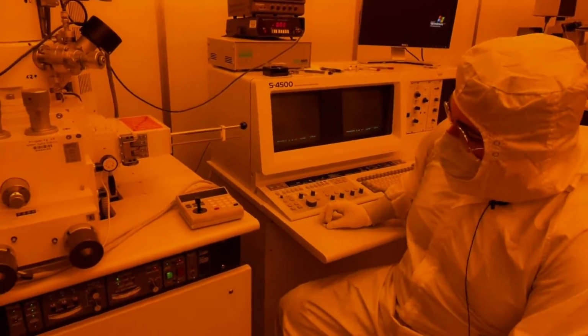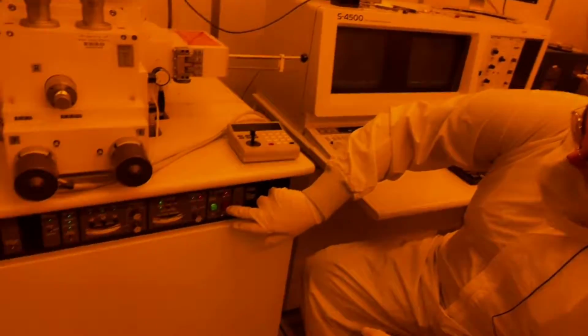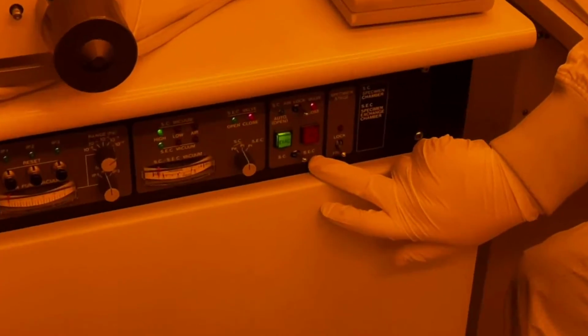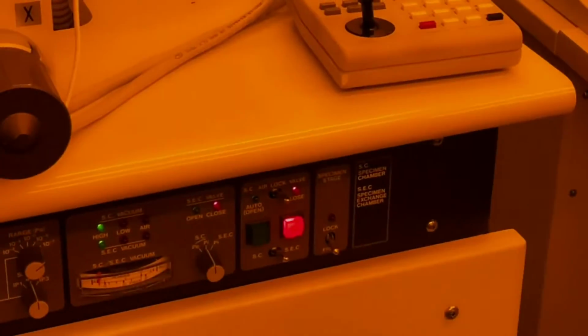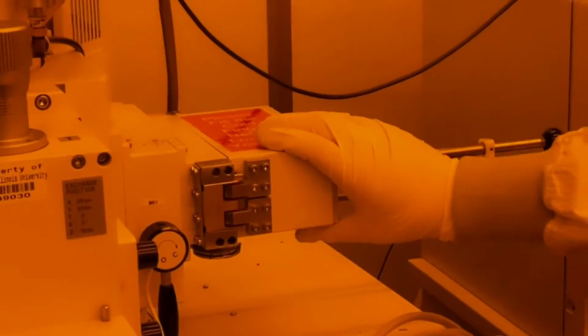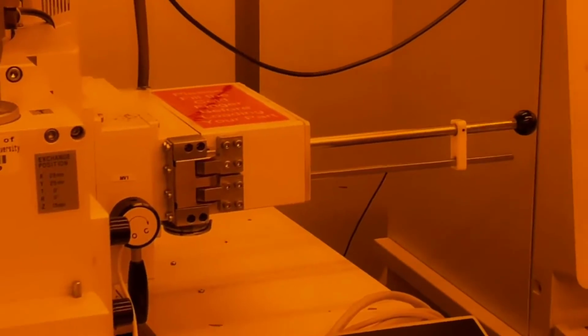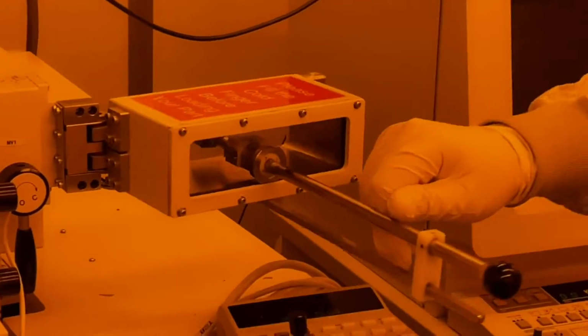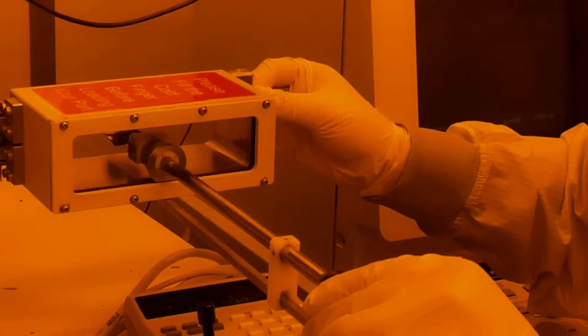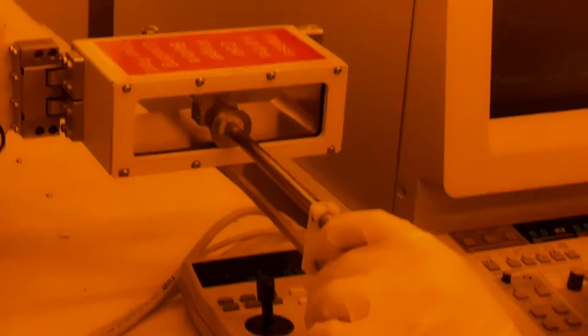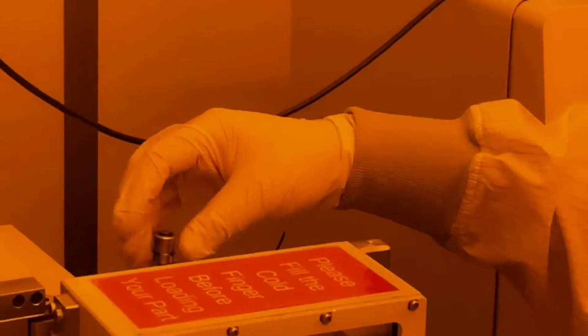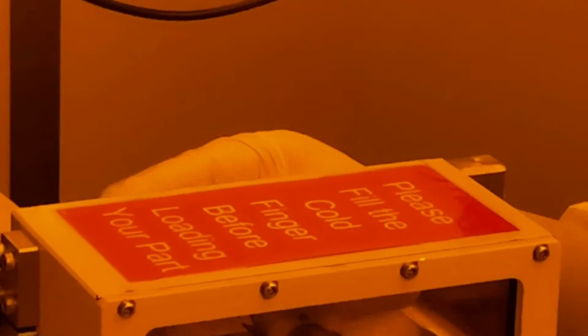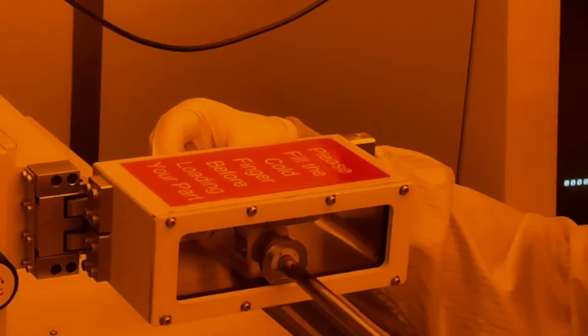So the first thing we do to load the sample, we're going to press the air button while the SEC switch is toggled. You can hear the pneumatics actuate. Now it's opening this up to the vent gas, which is nitrogen from the back. So now we can open the chamber, push in the exchange rod. Now we attach, that might be too tall. Yeah, that's going to be too tall.